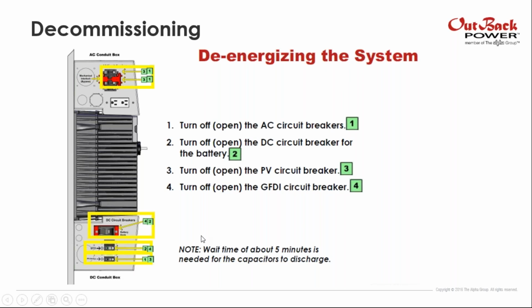If you see, when we did the commissioning, we turned on the GFDI first. Well, for the decommissioning, we have to turn off the GFDI circuit breaker at the end. Why? For the same reason. If you have a fault in your system and you have not opened the GFDI circuit breaker, that damage can be conducted to your devices. So this is one of the most important devices talking about protection, the GFDI circuit breaker.